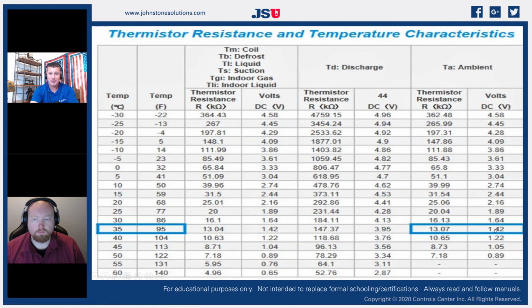So that thermistor is going to have, on a 95-degree day, a resistance value of 13 k ohms. If it's a discharge temperature sensor, it's going to be a little bit higher. It's going to be 147 k ohms. That's all. It's literally just measuring resistance across it, and it will be either accurate or bad. That's it. There's no in between. Either it is working or it is not.